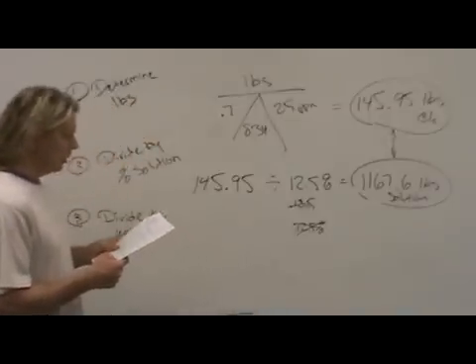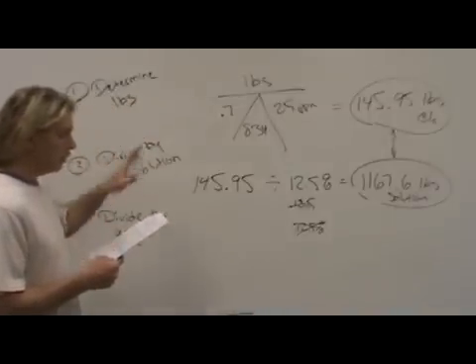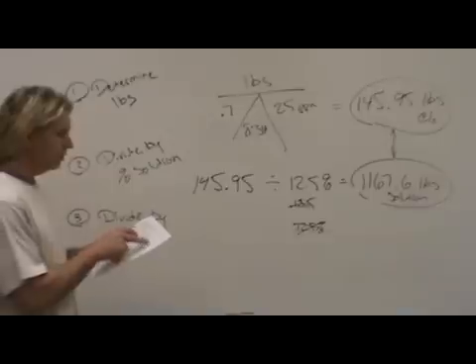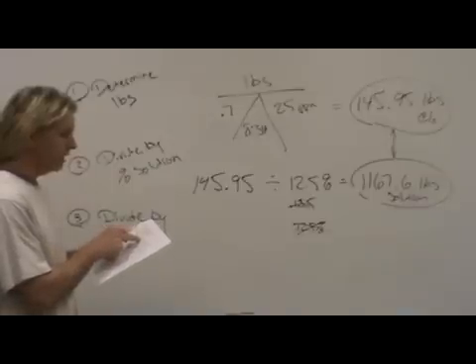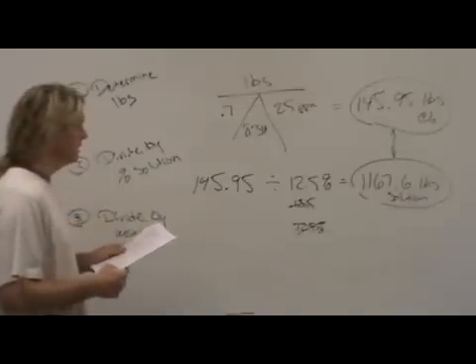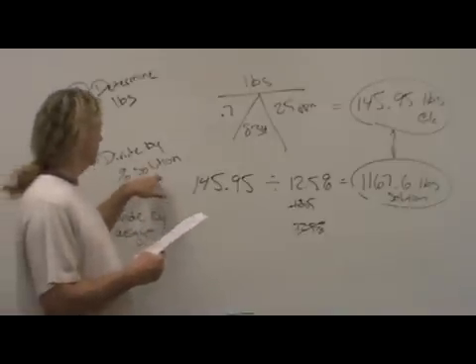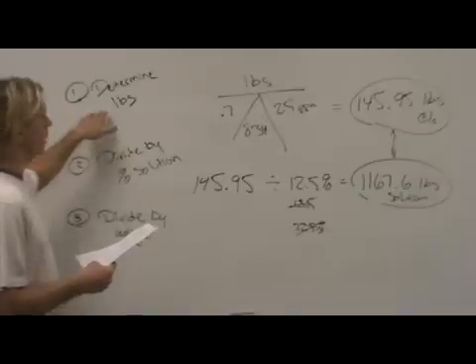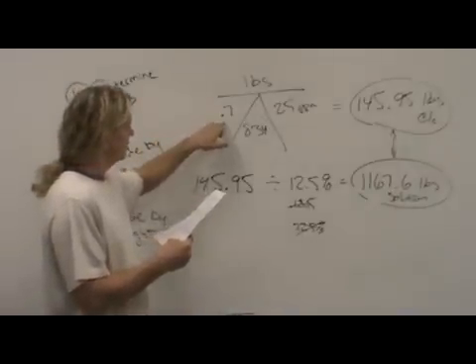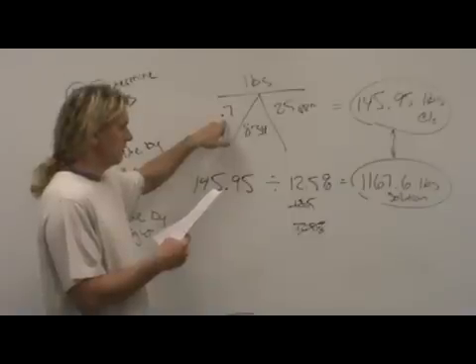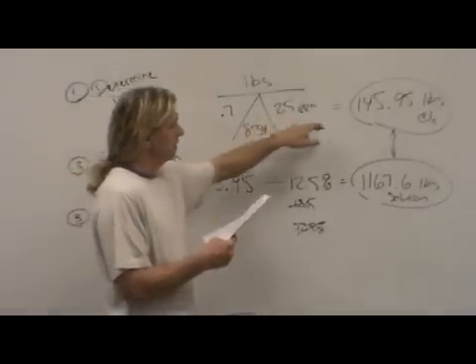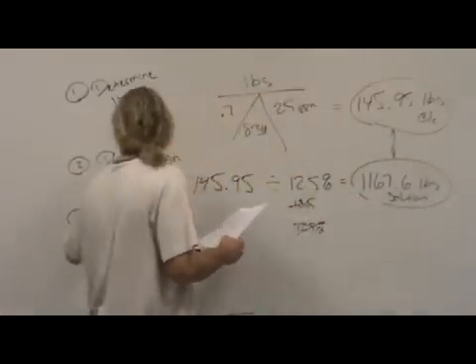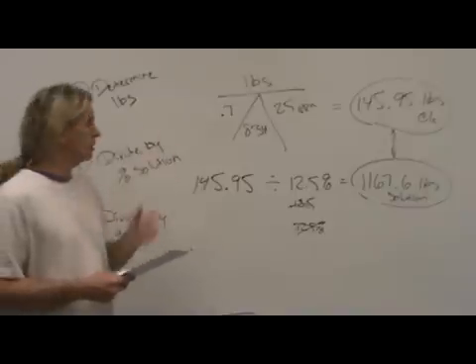This next problem is basically this exact problem taking it to the next level. A flow of 700,000 gallons per day requires a dose of 25 parts per million chlorine. If you're using 12.5% sodium hypochlorite, how many gallons of solution are needed? Instead of how many pounds of your solution, how many gallons of that solution? So you would solve the same way. Remember, you take that 700,000, convert it to a million gallons, 0.7 times 8.34 times 25. You get 145.95 pounds of chlorine.